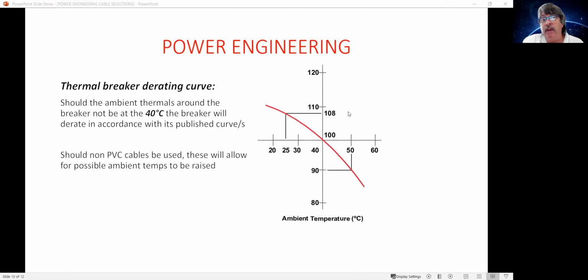And if you're going to go lower, as in this is 25 degrees, you can see that it'll hold 108 and offset. And this is all thermal type breakers. So if you're using PVC cables, be aware that you've got a variation in the performance of the breaker, which is offset somewhat by its actual thermal temperature.